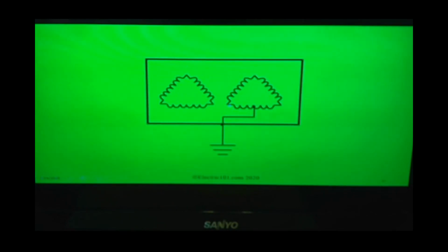I could have transformers that are delta-delta. Once again, that ground right there that connects the transformers is optional. I could have delta Y, Y delta. I could have all kinds of configurations. So transformers themselves, every one of these windings is an individual winding. All three windings here are secondaries. All three windings up here are primaries. All connected together. The label of the transformer will actually have a picture of the transformer on the label, and it will identify what's delta and Y. It'll identify the configuration, with delta Y being the most common.